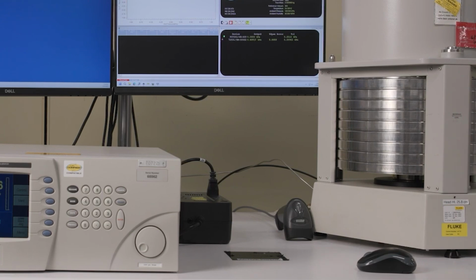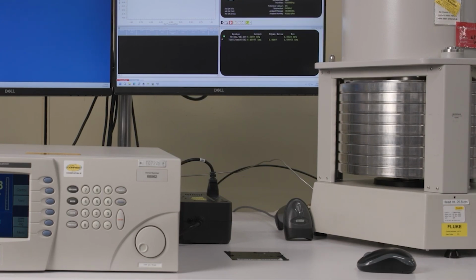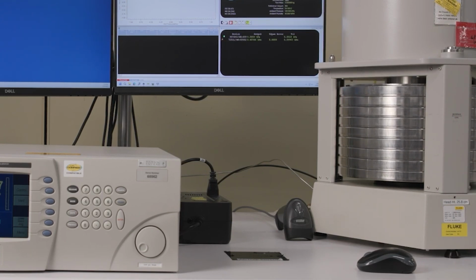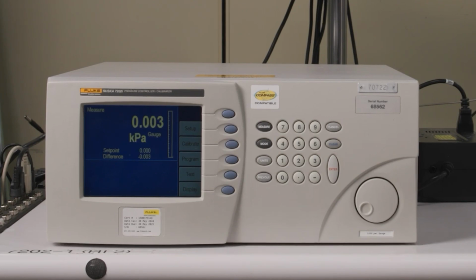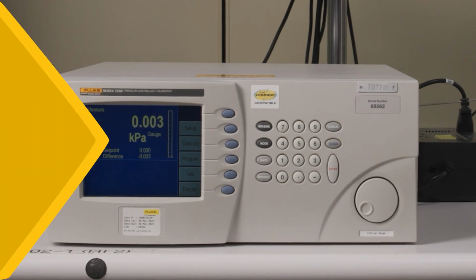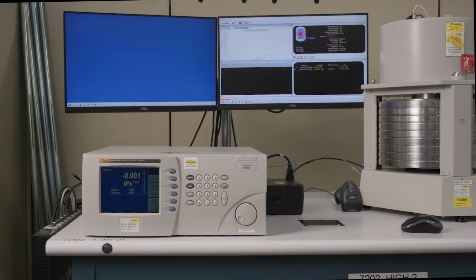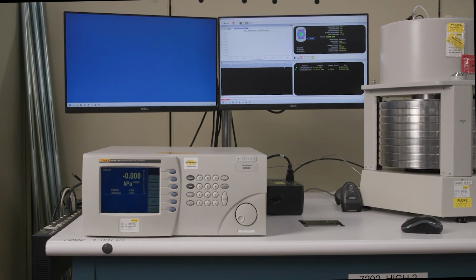It runs 3 pressure excursions to exercise moving components. After that, we zero the instrument using internal optics like lasers and mirrors. Once zeroed, Compass proceeds to perform the full calibration run. The system executes a series of 9 pressure points, ascending and descending, to assess linearity and hysteresis. Each value is captured and logged automatically.